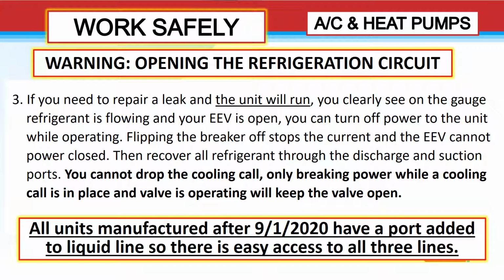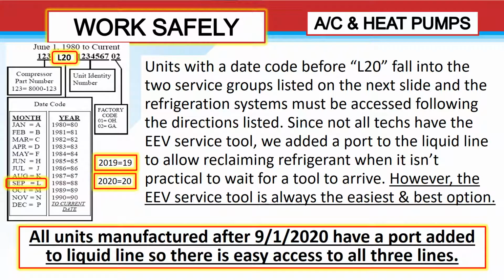And note that all units manufactured after September 1st of 2020 have an added port to the liquid line, so there is easy access to all three ports. Units with a date code before September of 2020 fall into two service groups, and they're listed on the next slide, and the refrigeration systems must be accessed following the directions listed.